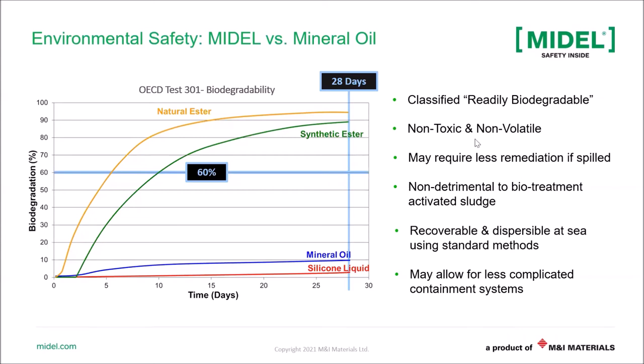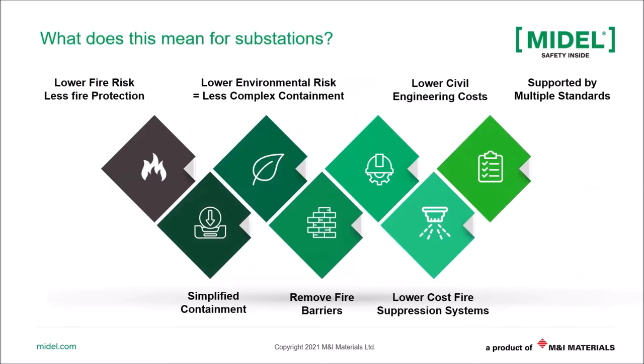The other thing is that MIDEL esters are non-toxic and non-volatile, and that they may also allow for a less complicated containment system to be around the transformer. But that would be dependent not only on the local state, but also on the federal regulations as to where the transformer is placed. So in summary, what I want to highlight is that when MIDEL esters are used in transformer application, they lower the risk of transformer fire from taking place, and less fire protection would be required, which would also mean less maintenance of the fire protection equipment.